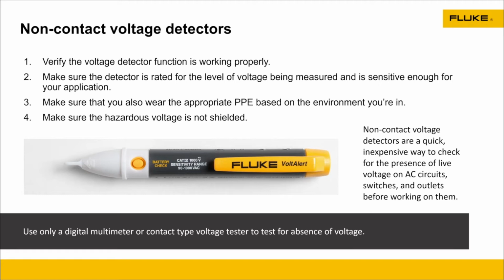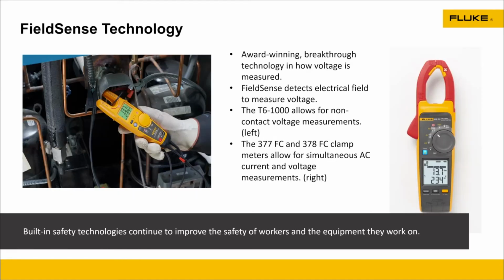And all this is really educational. Hopefully everybody takes some information back from this to say, hey, I need to be looking at my test leads, I need to be looking at my meter more, and making sure I'm working in the correct environment. Now, think about that non-contact I just talked about, and we'll introduce FieldSense. FieldSense is a Fluke technology. It basically has a sensor built into the meter itself, and it will measure voltage and current without using that metallic contact. This is a safer way of making voltage and current measurements without ever having that arc potential there.